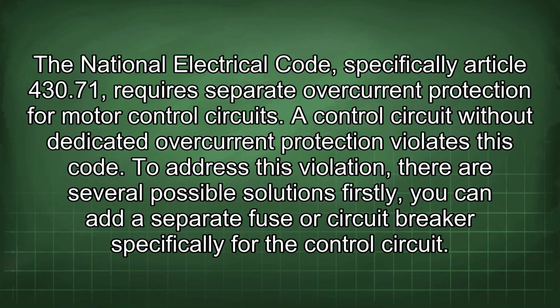The National Electrical Code, specifically Article 430.71, requires separate overcurrent protection for motor control circuits. A control circuit without dedicated overcurrent protection violates this code. To address this violation, there are several possible solutions.